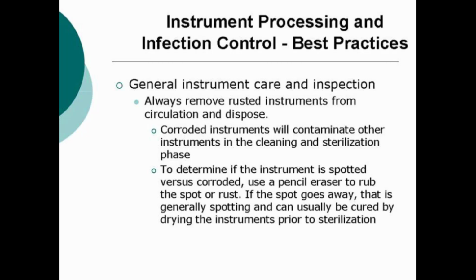To determine if the instrument is spotted versus corroded, a simple test is to use a pencil eraser and rub the spot or rust. If the spot goes away, this is generally spotting and can usually be cured by drying the instrument prior to sterilization. If it doesn't, it's typically rust.